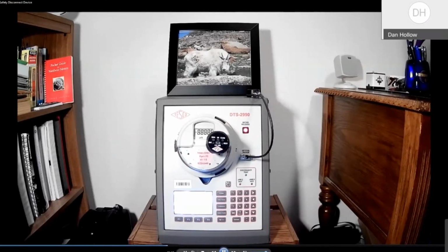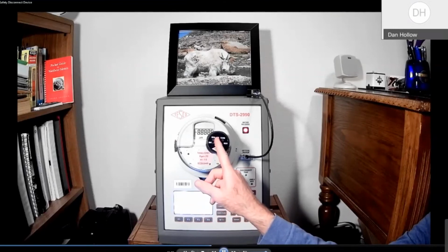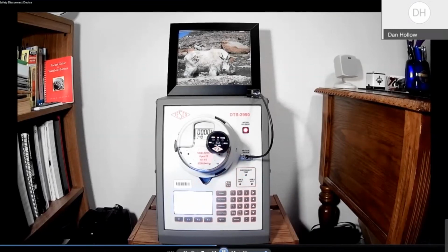It contains the passwords for this particular meter, which is what allows it to send a write command, which is what a service disconnect open or close command is. It's a write level command, so it requires an administrator level password, which has been programmed into this device and corresponds to the password in this meter. We go ahead and turn on the power. It is naturally sleeping, and turning on the power wakes it up, in this case for about 10 minutes before it shuts off again. That's a programmable feature.